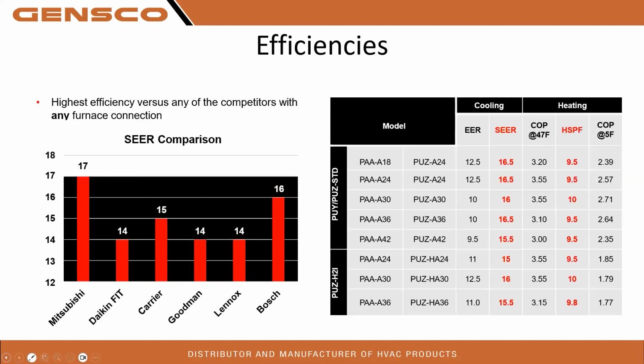Efficiencies. Mitsubishi Intelli-Heat is beating all of our competitors by quite a bit on the SEER ratings, as you can see here. Due to AHRI requirements, all the testing is done with the worst wattage blower possible. So this is a PSC belt-driven motor versus ECM motors. We're seeing efficiencies as high as 20.5 SEER, but because we have to rate them based on the worst-case scenario, we're seeing about 17 SEER on a belt-driven motor. So that's pretty darn good.